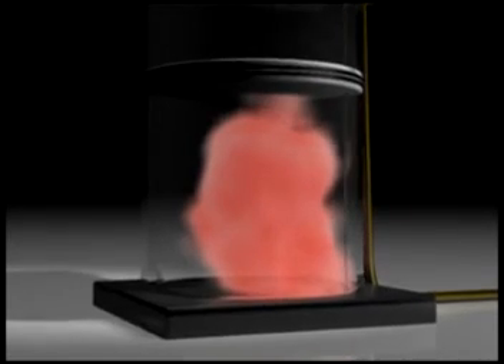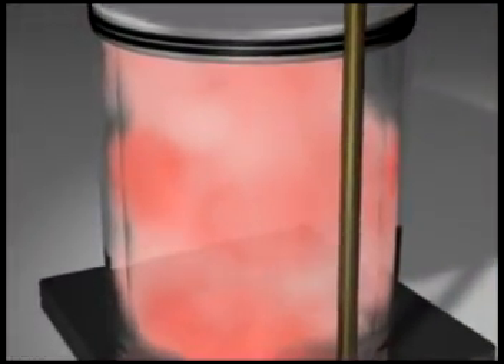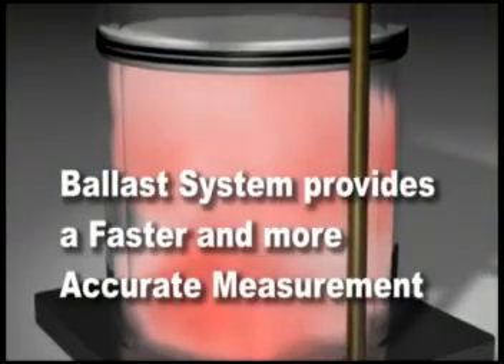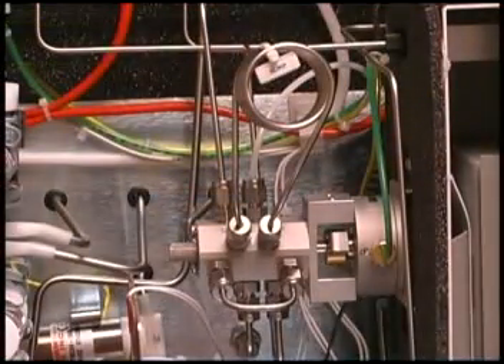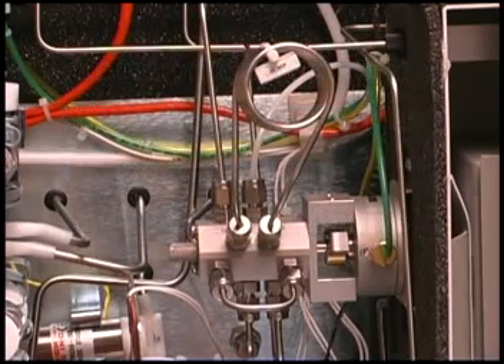During analysis, combustion gases are collected and equilibrated using the ballast volume. Once the combustion phase of the analysis has completed, a gas sample is taken, scrubbed, and an exact measurement is made. The ability to measure a smaller amount of combustion gas allows a faster, more accurate measurement to be made. The TruSpec has a much lower reagent usage and offers greatly reduced costs compared to other competitive systems.